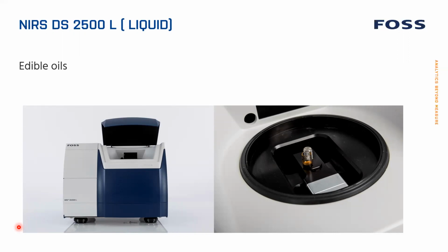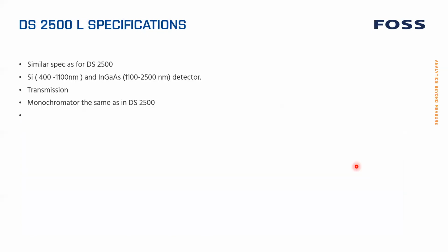DS2500L for liquid. The only application we have here is edible oils. And as you can see, the instrument is in principle the same. It's a DS2500, but instead of having the rotating part for this cup, it has a holder for vials, cuvettes here. And this holder is easy to change depending on the vial or the cuvette you're using. Specifications are similar to the DS2500. It's using a silicon detector for the lower range, and here it's using the indium gallium arsenide detector for the high range. It works in transmission, and the monochromator itself is the same as in the DS2500.